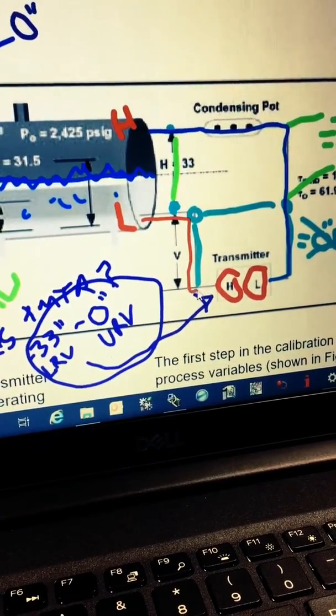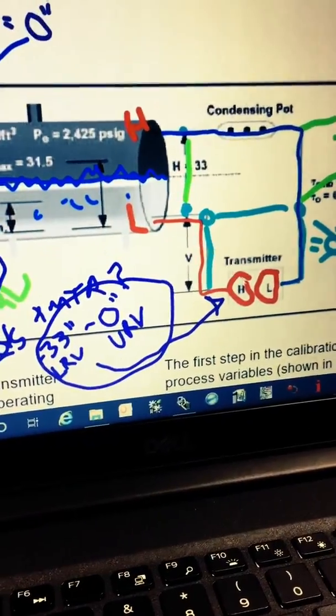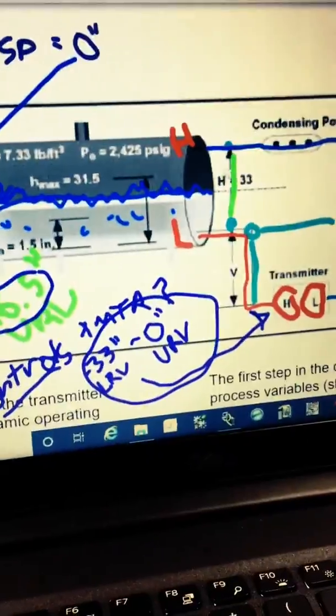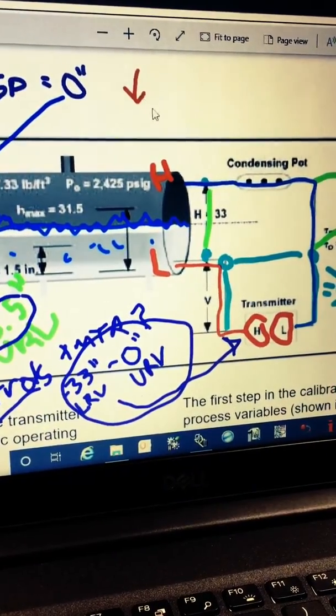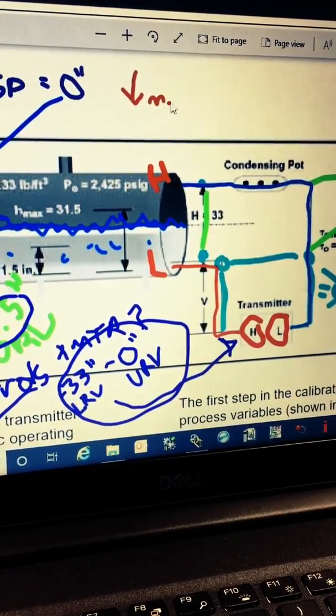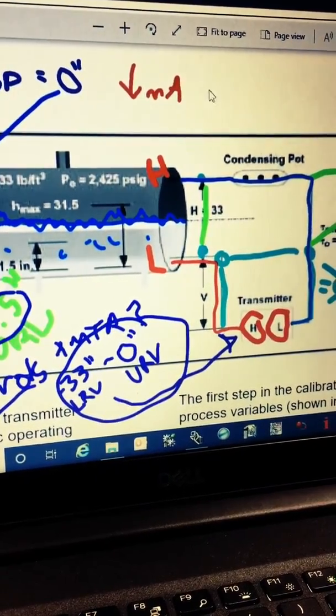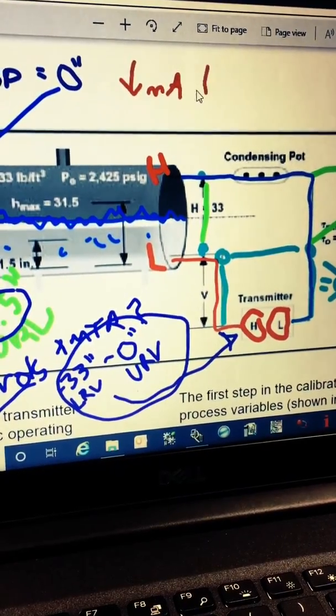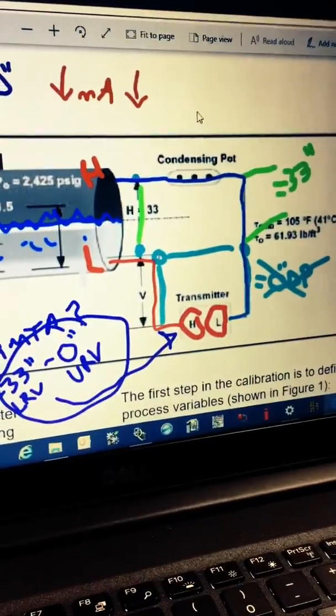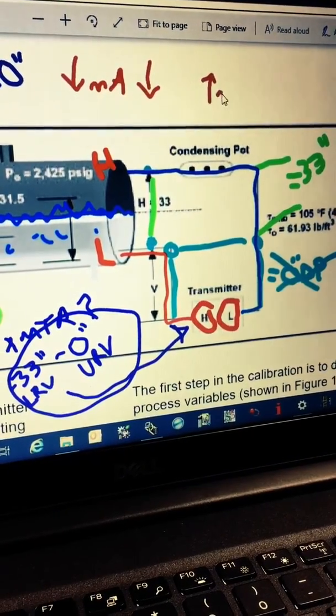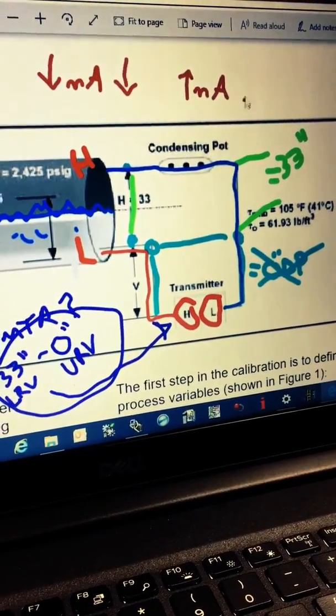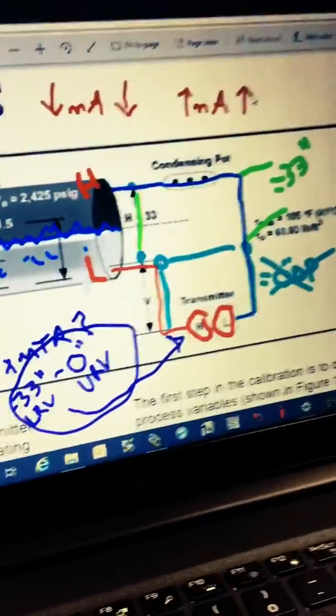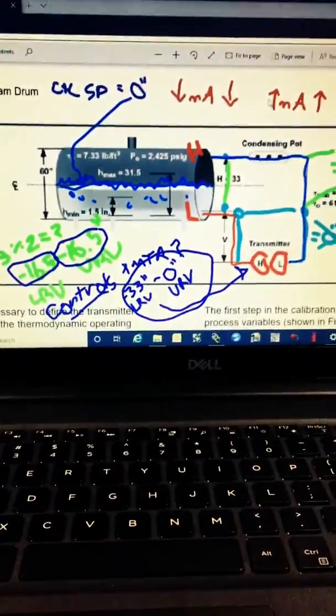And then, as the low-level leg, as that water goes up and down in the drum, the pressure on that leg is going to change. And the level signal from the transmitter to the control is going to change. Basically, as we go down in level, we want to go down in milliamp value. And, as we go up in level, we want to go up in milliamp value. Because we always want our process to go more positive when it comes to level, as the level goes up.